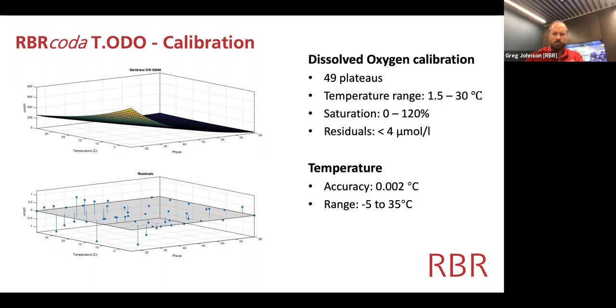The user calibration is easy to do using our Ruskin software that you might be connecting the instrument to. You make the instrument perform the same measurements in 2 different levels of oxygen. So you can take an oxygen bubbler, for instance, an aquarium bubbler like in the fish tank behind me, bubble that through a bucket of water, and that will saturate the water after 15 minutes, 30 minutes. And you can use that as a 100% saturation level.